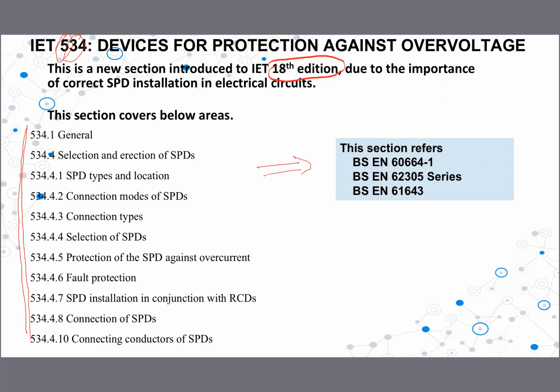So for this overvoltage protection and selection of SPDs, it refers to these three standards as well. It gets information from these three standards: BS EN 60664-1 and BS EN 62305 series 1 to 4. This is about lightning protection, surge protection, and those things, direct and indirect lightning. And BS EN 61643, right? It refers to these standards also to get the information. Actually, these areas we can discuss down the line, right?